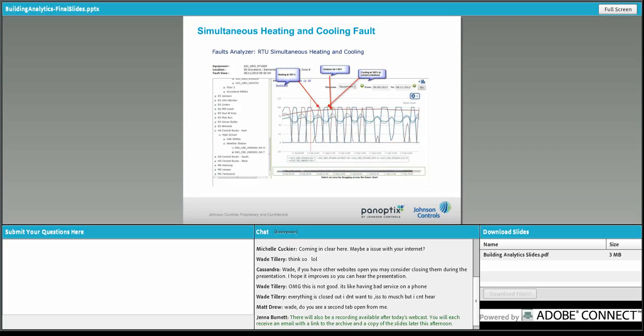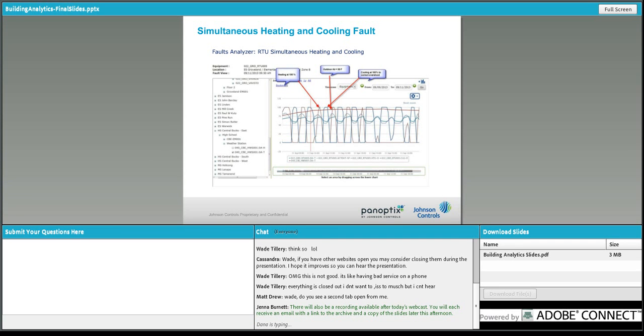What we have here is a piece of equipment calling for heating and cooling at the same time. Unless there's a specific dehumidification strategy in place, this is probably indicating a fault either in the equipment or the control strategy. This is a simple condition met by looking at two different variables and writing a rule to detect it.